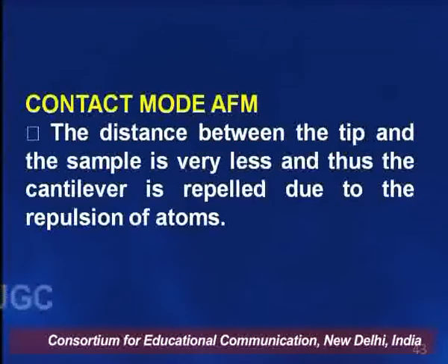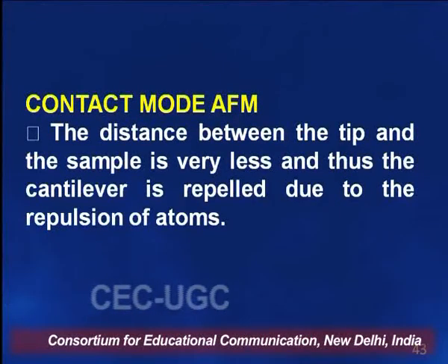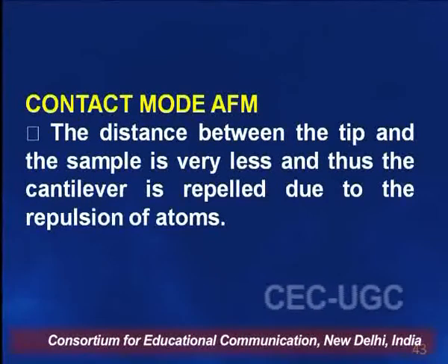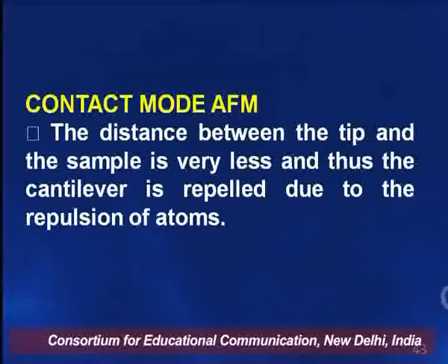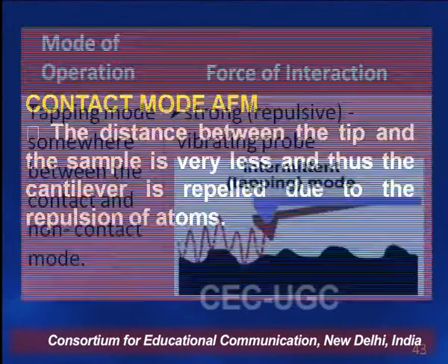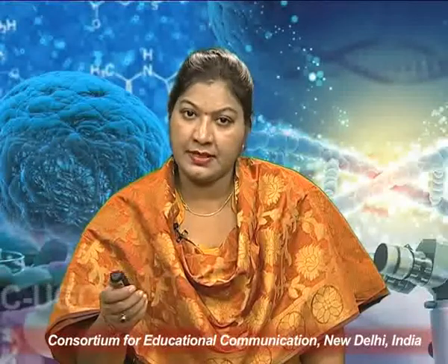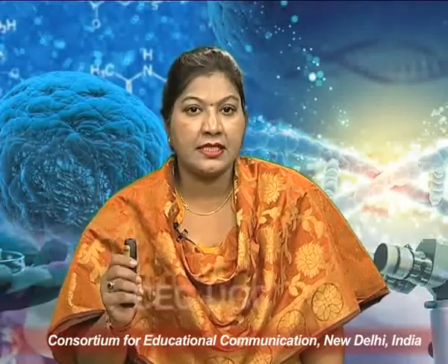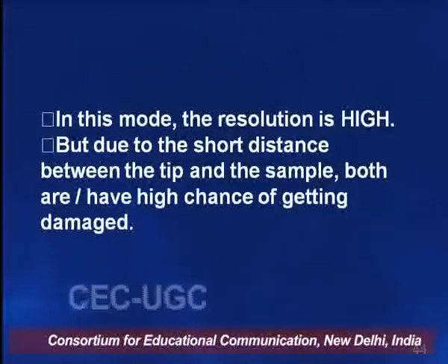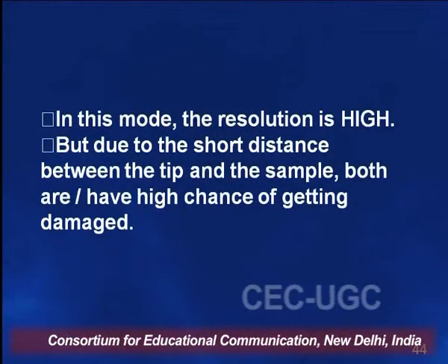So these are the 3 modes, and we discuss further the contact mode. The distance between the tip and the sample is very small in this contact mode. Thus the cantilever is repelled due to the repulsion of atoms. There is a force of repulsion and the distance is very small between the sample and the tip to scan the surface. In this mode the resolution is very high because the distance between the tip and the surface is very small, so we can get good resolution by using this contact mode.